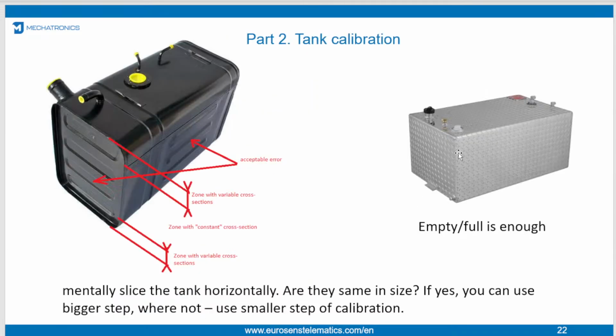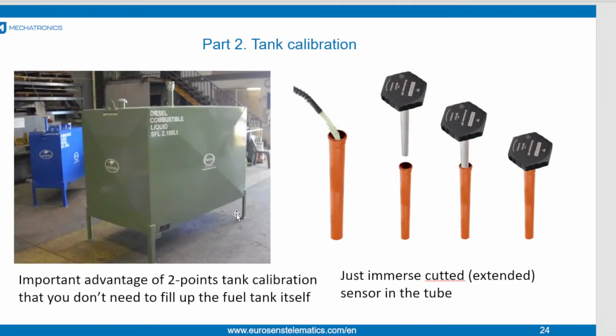And again, a rectangular tank can be almost purely rectangular, and you can use only 2 points, empty and full, because all cross sections are the same. It can help you to choose the optimal number of calibration points. Very important: if we have the possibility of 2-point tank calibration, like this rectangular tank, we don't need to fill the tank till full to calibrate it. We can emulate the full tank state by immersing the sensor in the tube, like during sensor calibration. So we only need to know the exact tank volume for tank calibration.